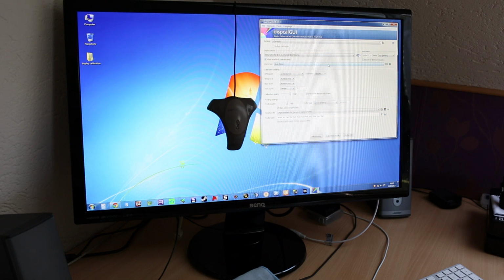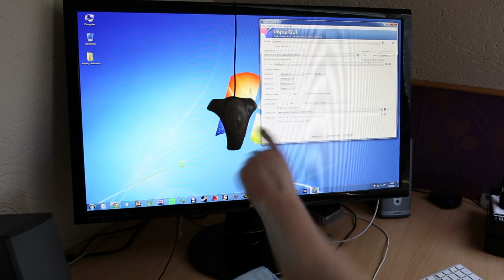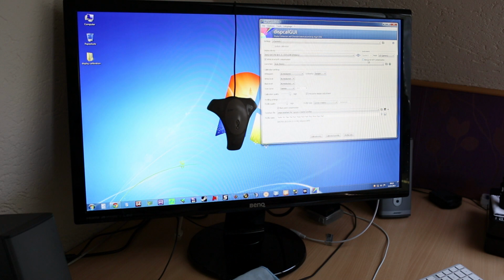It's going to take a heck of a long time, 2.5 hours is usually what it takes for me. Then black drift calibration or compensation is the correction for a warming up measurement device. It's always going to measure a black value to make sure it's still the same black, and if it's not, it's going to compensate for that, because the sensor in the Spyder3 increased in temperature. So we want to make sure that's counteracted.